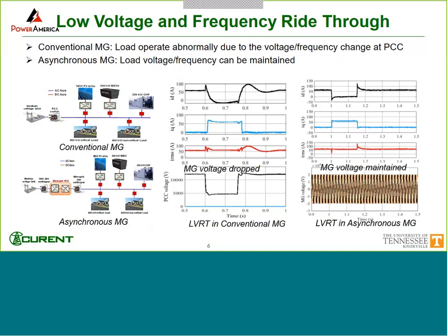This is an example, and we have some simulation work just to show it. It is an example of low voltage and low frequency ride-through, and low voltage ride-through in particular, in a conventional microgrid versus the asynchronous microgrid. This side shows the low voltage ride-through in a conventional microgrid, and this side shows the corresponding one in the asynchronous microgrid. As you can compare, because the asynchronous microgrid is isolated from the conventional grid through this PCS, the voltage magnitude, at least in this case, is very well maintained. So you will not see a voltage drop as shown on the left-hand side.